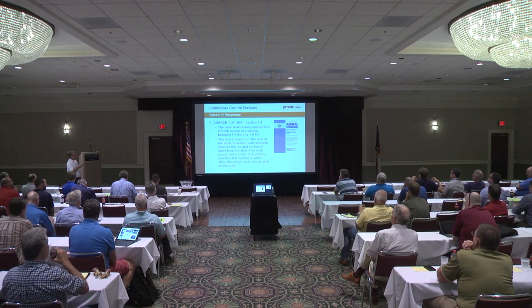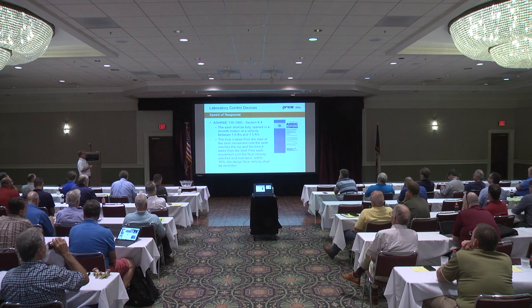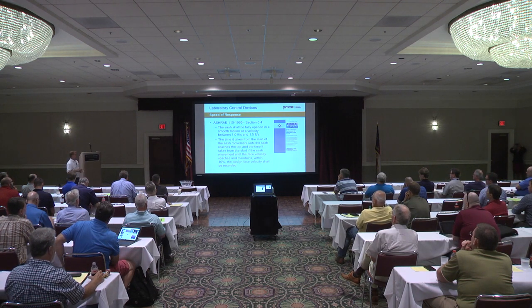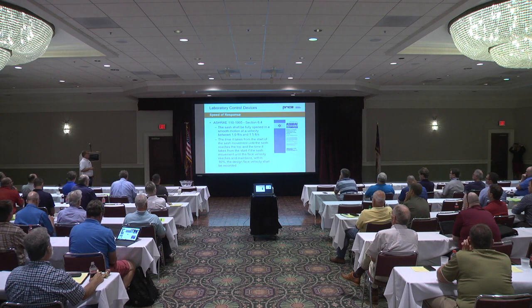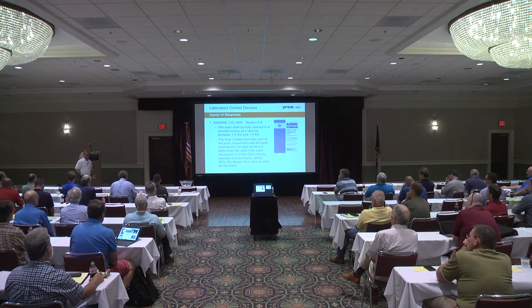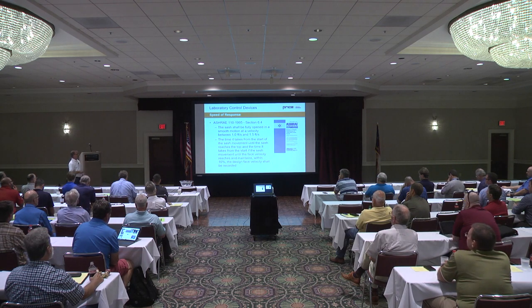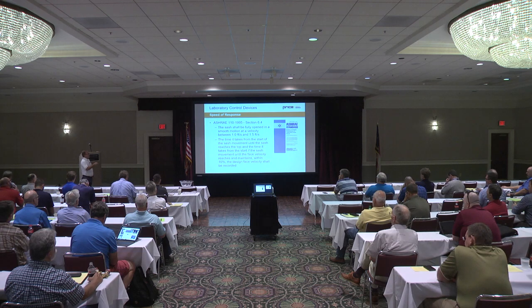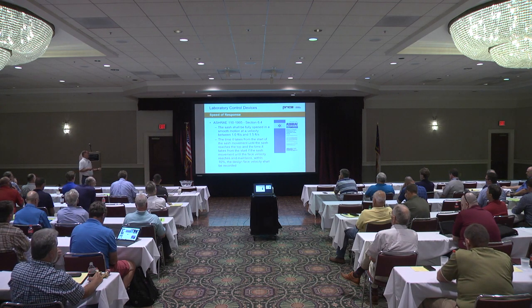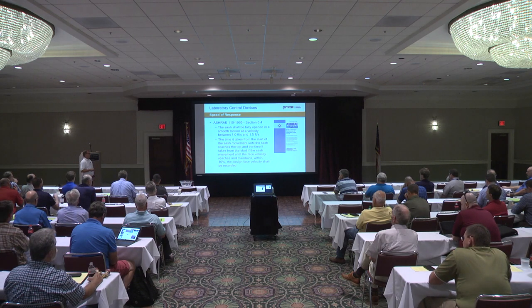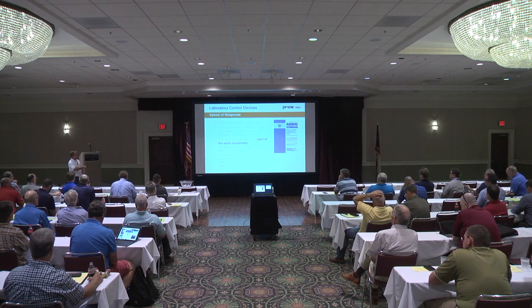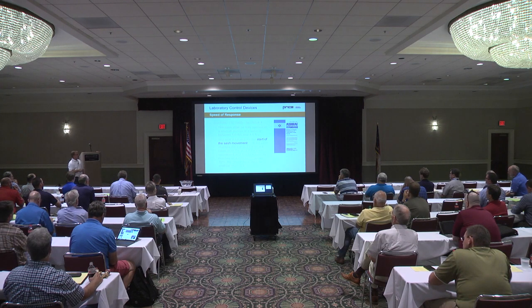So another speed of response, this is the ASHRAE standard. The sash shall be fully open and smooth. So when you're testing fume hoods, it states that the way you're supposed to operate the sash is fully open with smooth motion at a velocity between 1 foot and 1.5 feet per second. Basically saying you're not throwing the sash full open as quick as you can or lowering it as quick as you can. There's a procedure for opening and closing the sash for testing. The time it takes from the start of the sash movement until the sash reaches the top, and the time it takes from the start of the sash movement until the face velocity reaches or maintains within 10% of design face velocity should be recorded. So again, it's from the start of the sash movement. Okay?